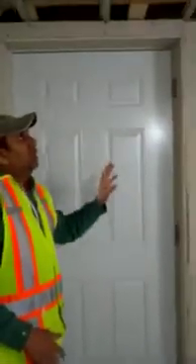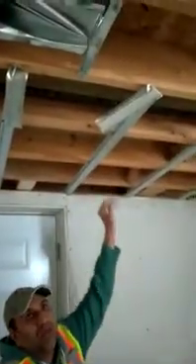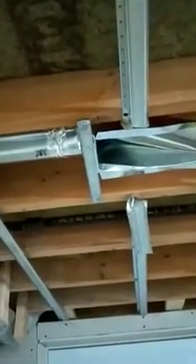That is a legal basement door that we installed here, and these are the resilient channel, called a sound bar. We also did Safe and Sound. If you see here, there's Safe and Sound. That means if someone is walking upstairs, the sound will be controlled. It won't come down. And we did a heating system. You see the heating coming here, one hook-up from the main plenum, and also there's a return air. It's a must. That return air is a must in a legal basement suite.